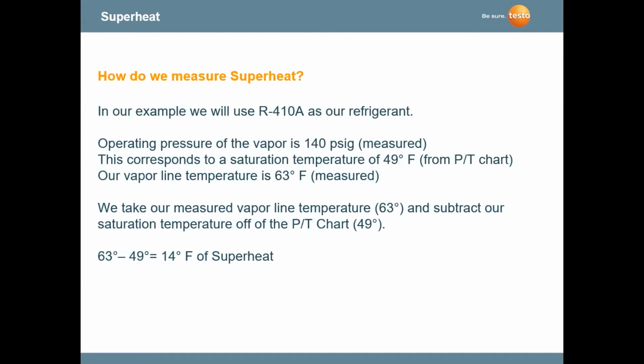140 psi-G. We use our pressure temperature conversion charts. We see that 49 degrees Fahrenheit is the saturation temperature. And we still have to use a temperature sensor to get the vapor line temperature. And we do a little bit of math. We get 63 minus 49 equals the 14 degree superheat.